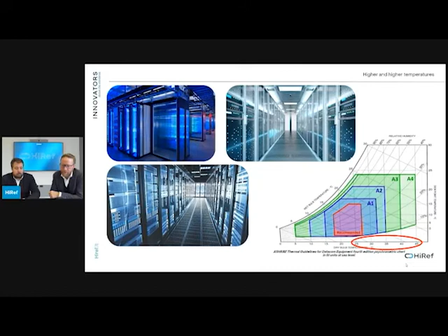Another aspect is related to the diffusion of liquid cooling systems, which are becoming more and more interesting for the market, especially for high performance computing. We have to think about direct-to-chip cooling systems, shown on the left side, but also immersion cooling systems, possible with single phase or double phase. All these liquid cooling systems give the possibility to increase the power density per rack up to 100 kilowatts per rack.